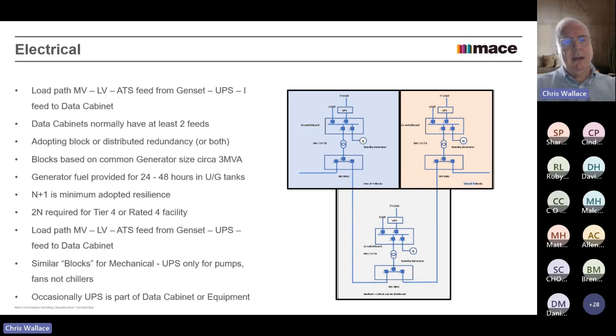The generators would normally, again, depend on what you want and where you are, whether you're following just some sort of specification from the client, or some other paper that you're trying to follow, like Uptime or TIA. But typically the fuel storage is underground tanks for between 24 and 48 hours, sometimes up to 72 hours. But that's when you think of, if you've got a large data center with a lot of generators, and you're running underground tanks of fuel for a lot of big generators, you end up with a huge tank farm and a huge supply of oil sitting there. And then you potentially have problems with the oil sitting too long between usage, and you end up with fuel scrubbing and things like that. But no, this is just a general thing.